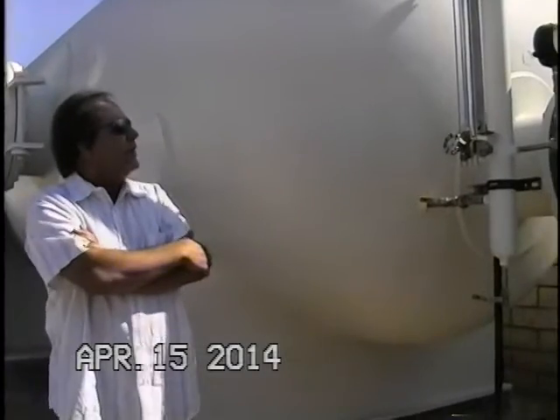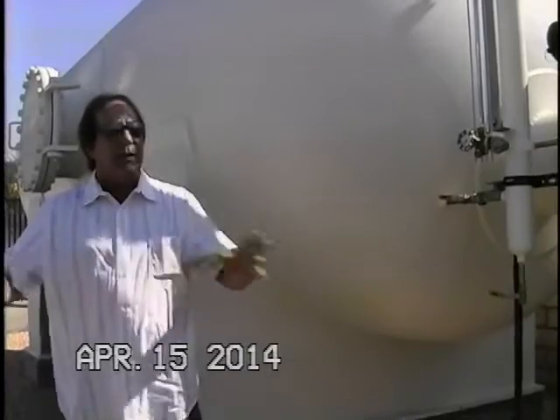Any questions? Find any scaling issues on the RF probe? No, and I know you've got recycled water here. This probe has a Teflon coating on the outside of the probe. We haven't had it, because you've got fairly clean water here. There's not a bunch of high solids or things of that nature in your particular system. It's not a bad idea that maybe once a year you clean the probe off.